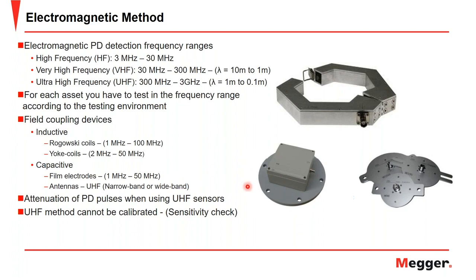And here's some examples where you have a flange sensor or window sensors that can be retrofit to GIS systems for PD measurements. When we talk about the unconventional methods, though, attenuation of the PD pulse is a real issue when using the UHF sensors. And attenuation is dependent on many different aspects, and that can be frequency, the geometry of the asset, reflection and refraction, the conductor material, as well as the mode of the PD transients themselves. And another big takeaway for the UHF method, or for the electromagnetic method, is that it cannot be calibrated.